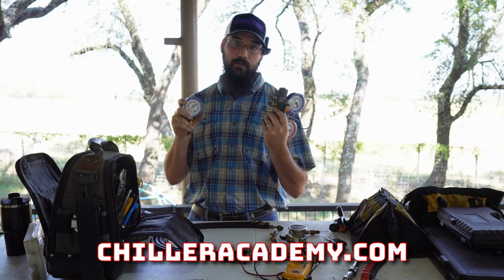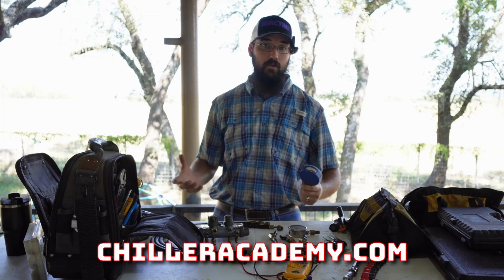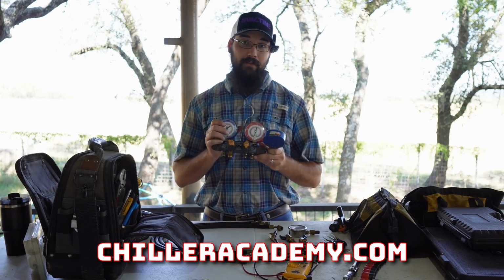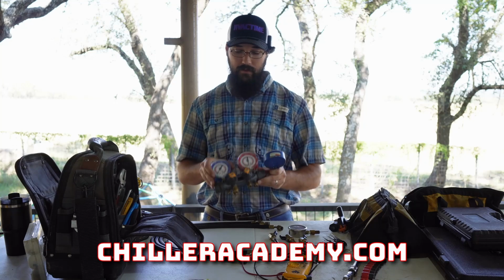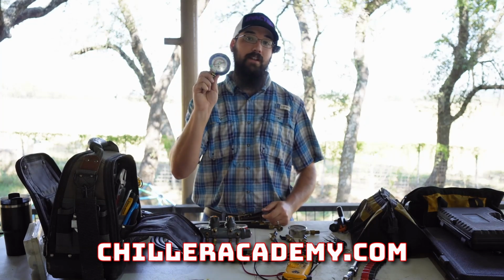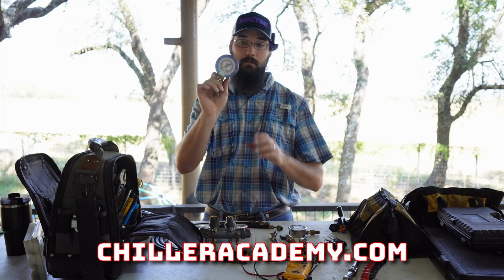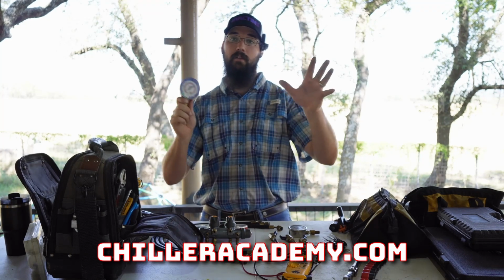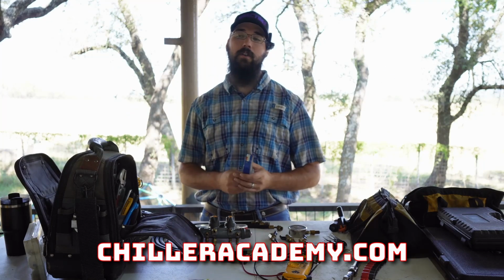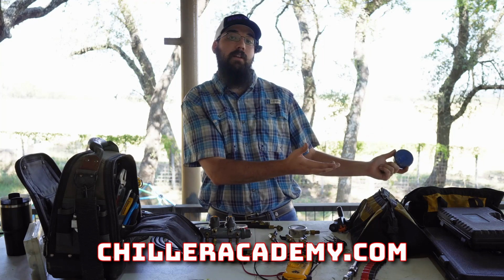So I moved from manifolds, especially when you start dealing with chiller systems and get into air-cooled or large centrifugals. You either need really long hoses, which is not reasonable, or a set of stubbies. This is what I did. I've got multiple sets of these stubbies so I can hook up to every circuit and see the whole machine's pressures just by walking around. A lot of the time these are on machines that didn't have display readouts.